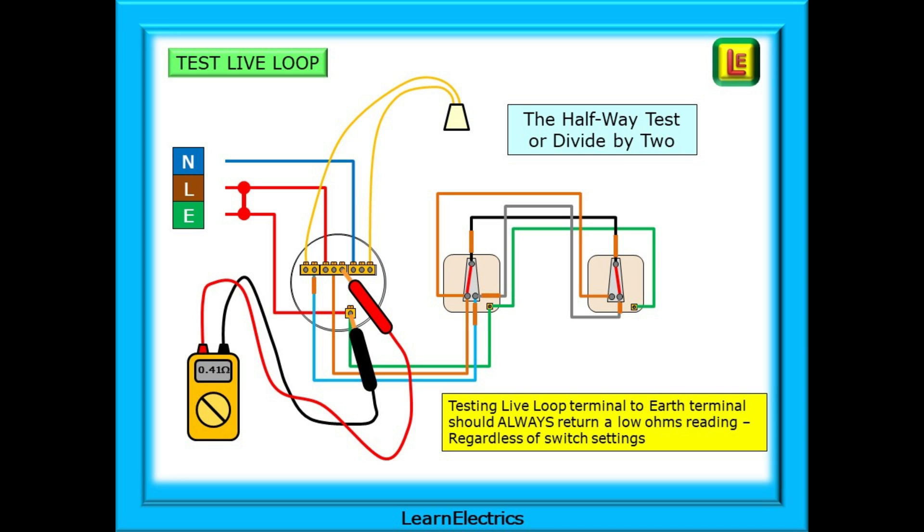Therefore, with the link between the line and CPC at the consumer unit still in place, we can test at the ceiling rose. Live loop to the earth terminal should always give a low ohms reading. Always, regardless of the two-way switch settings, live loop to earth will always be continuous in a good circuit. If it is continuous, 0.41 ohms as shown here, then the first part of the circuit is okay. The problem is with the wiring after it comes into the ceiling rose, or again, how the test meter is set up. If you have an OL or maximum reading, the problem is between the ceiling rose and the consumer unit. This is a good test to remember for lots of electrical problems. If you can find a suitable place to test mid-circuit, you can quickly keep dividing by two and focus on where the problem is.